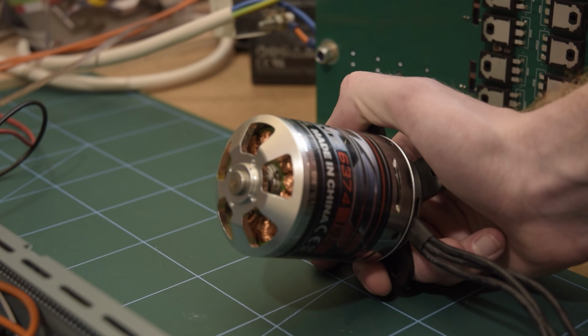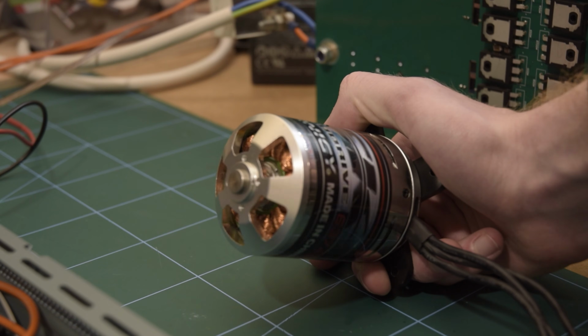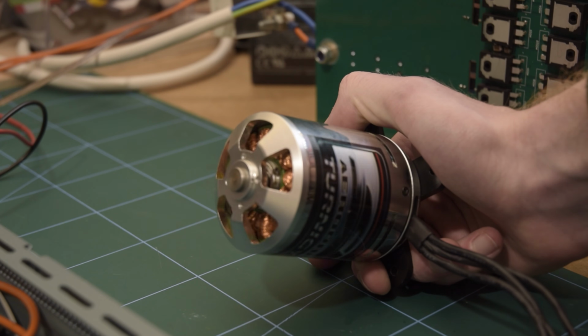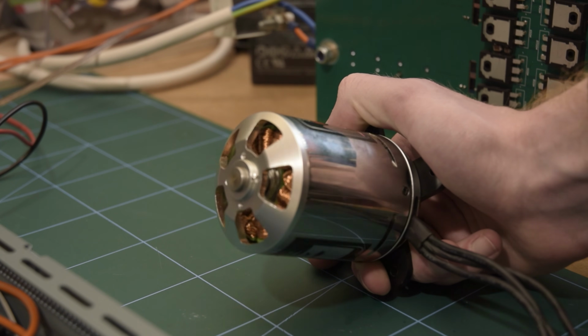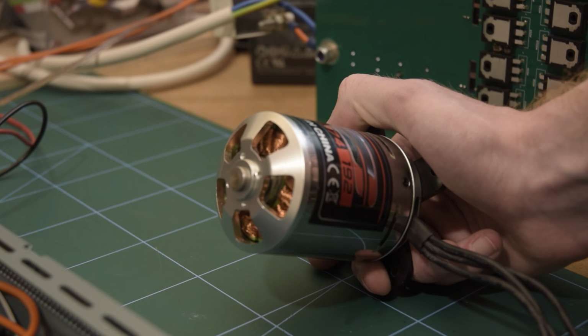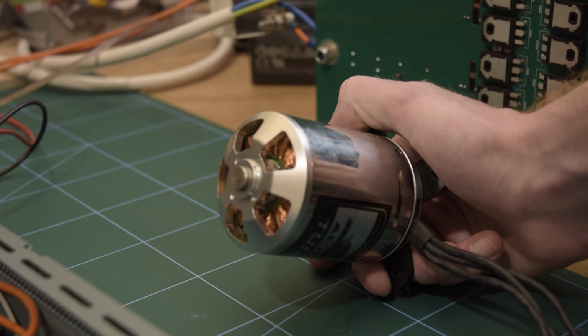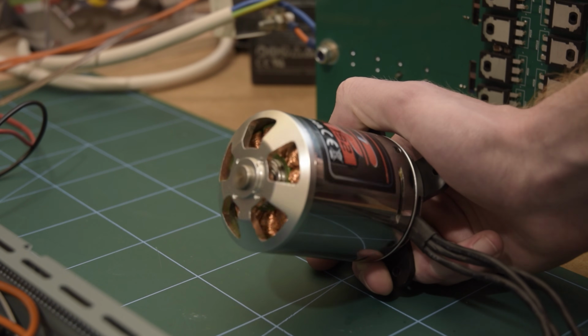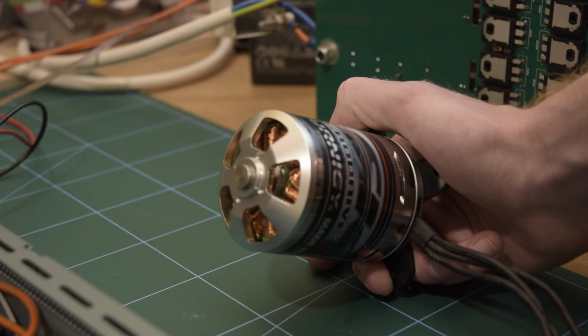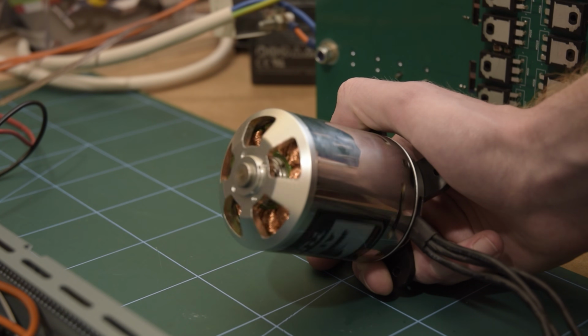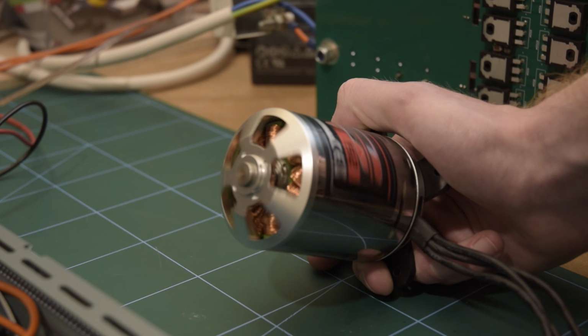So if I just hold this here and turn on the high voltage, let's see what happens. You can see it slowly turning. The reason it's turning so slow is because the frequency of that 3-phase I showed you on the scope is pretty low. Again, I can turn the knob on the front of the inverter and speed up my motor - there we go, faster and faster.